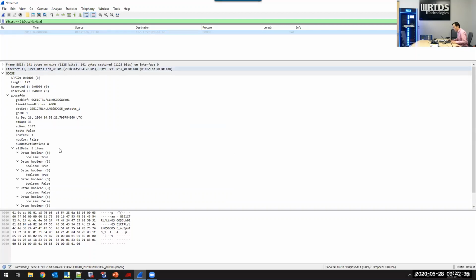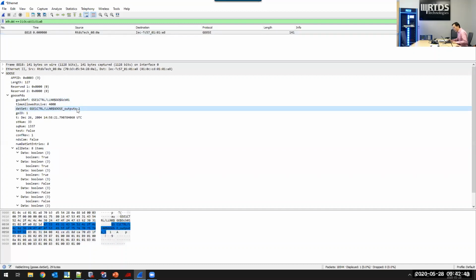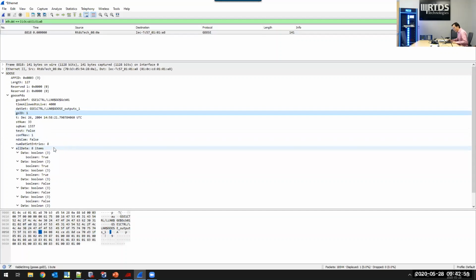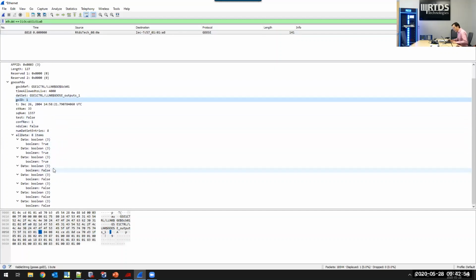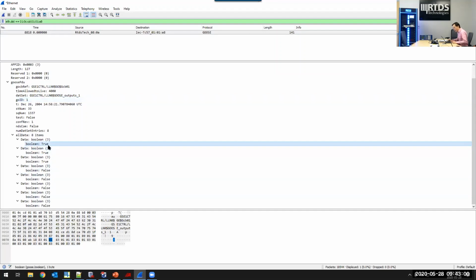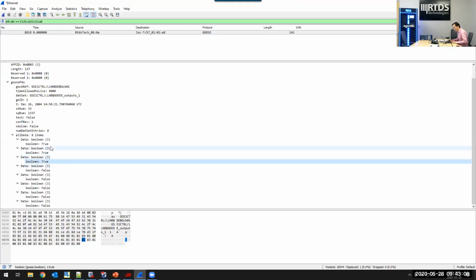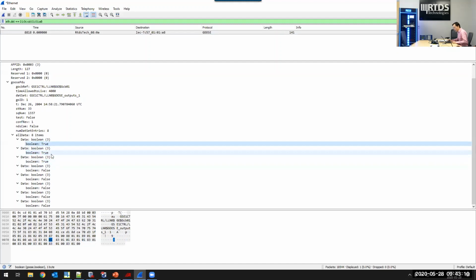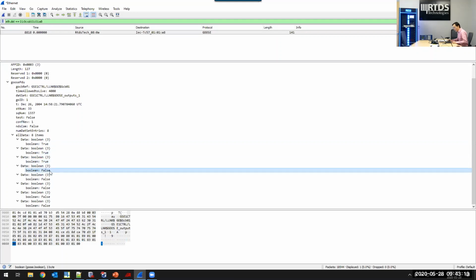Now we can do a quick check and go over some of the parameters here, so you can find your data set that matches your configuration, and the Goose ID. There are 8 items, even though we're only using 4, but the data set contains 8 items. The top 3 correspond to the status of the breaker, so they should be all on right now at the steady state. That is confirmed, and there's no trip, so there's no permissive trip either.